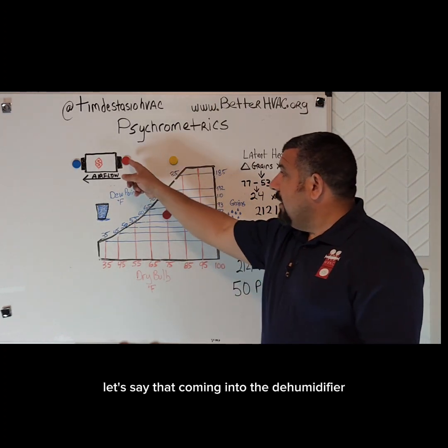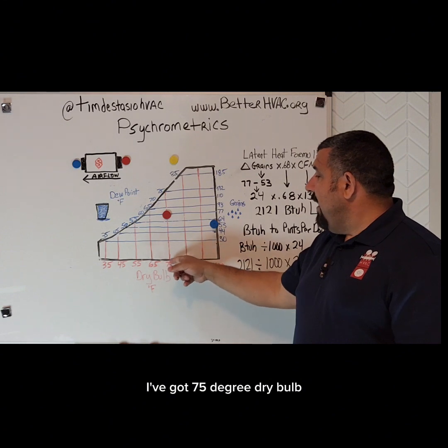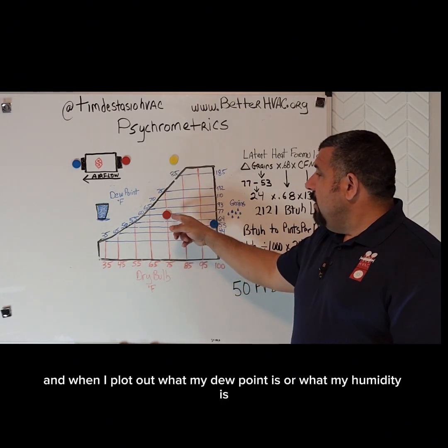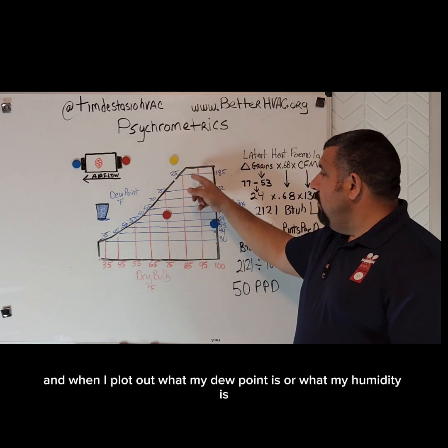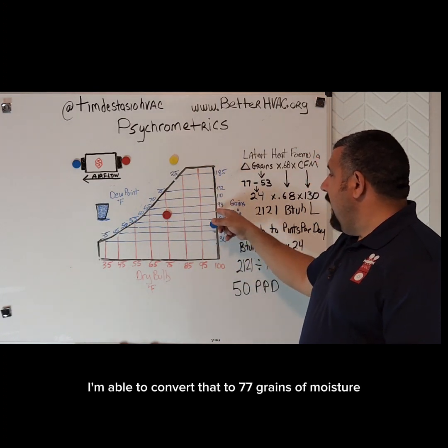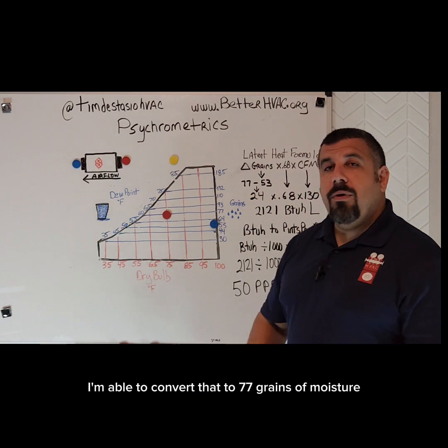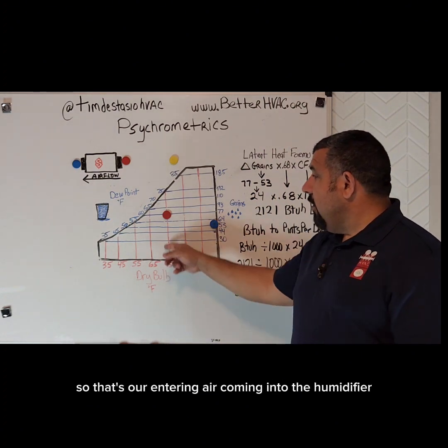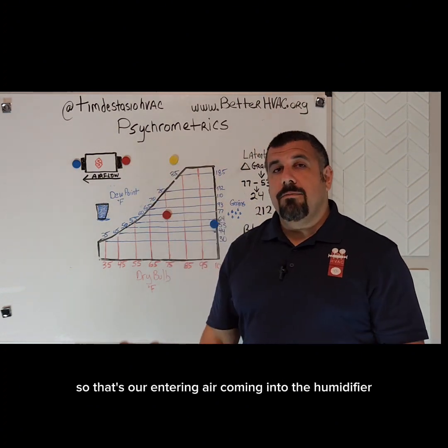Let's say that coming into the dehumidifier, I've got 75 degree dry bulb. And when I plot out what my dew point is or what my humidity is, I'm able to convert that to 77 grains of moisture. So that's our entering air coming into the dehumidifier.